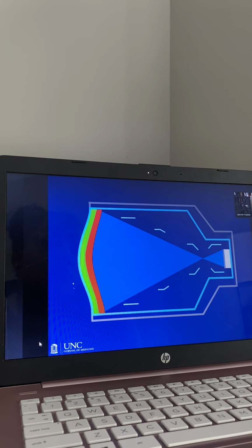So here we've got that curvature I was telling you about. If we use the entire diameter of this input phosphor, for our example, this would be like the 30 centimeters. So we're using the entire diameter. You can see this represents the electron beam. This is the focal point.